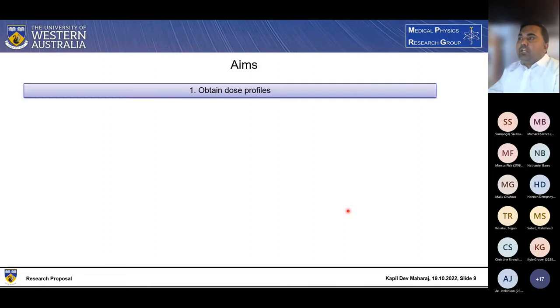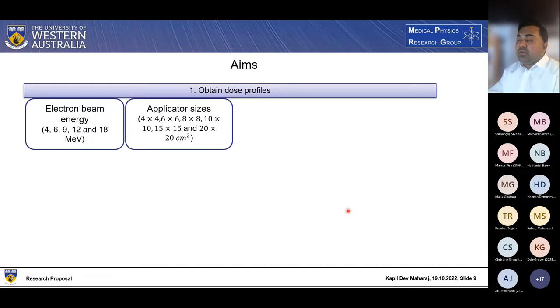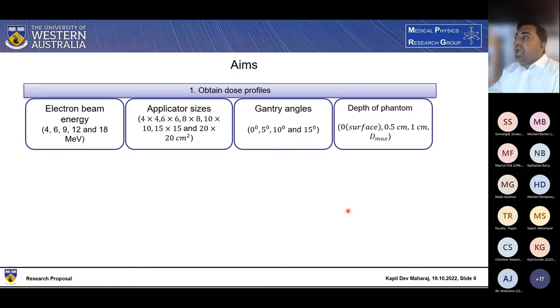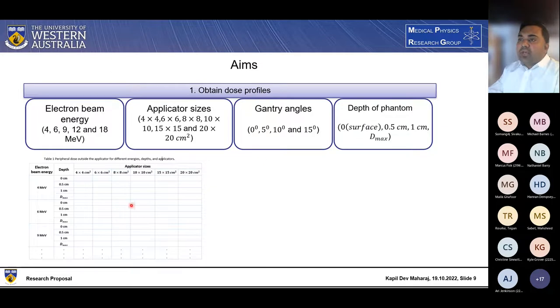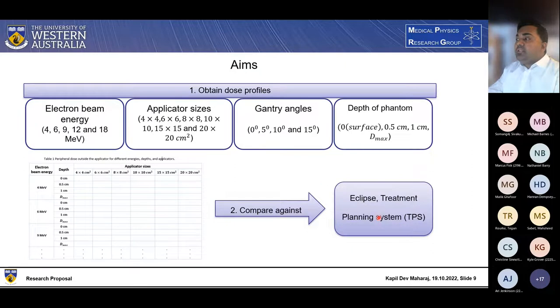So in terms of the aims of my project, I will obtain the dose profile using electron beam energy of 4, 6, 9, 12, and 18 MeV and using the different applicator sizes such as 4 by 4, 6 by 6, 8 by 8, 10 by 10, 15 by 15, and 20 by 20 centimeters square. Gantry angle at 0 degree, 5 degree, 10 degree, and 15 degree, and at depths of 0, 0.5, 1, and D max. After obtaining the dose profile, I will produce the data which could look like this, and then I will compare this data against my treatment planning system Eclipse.